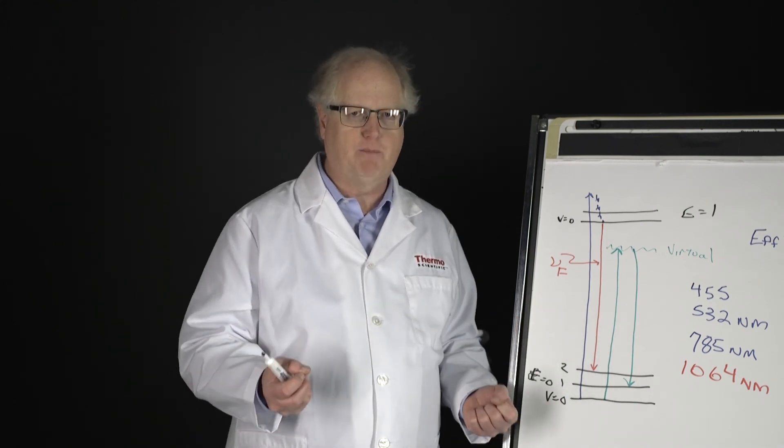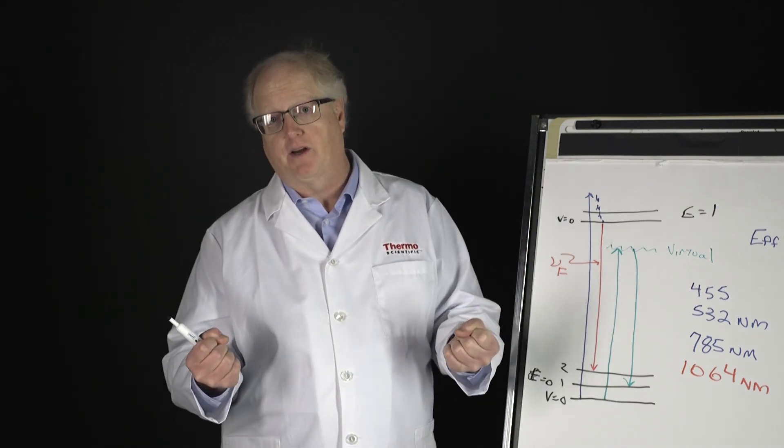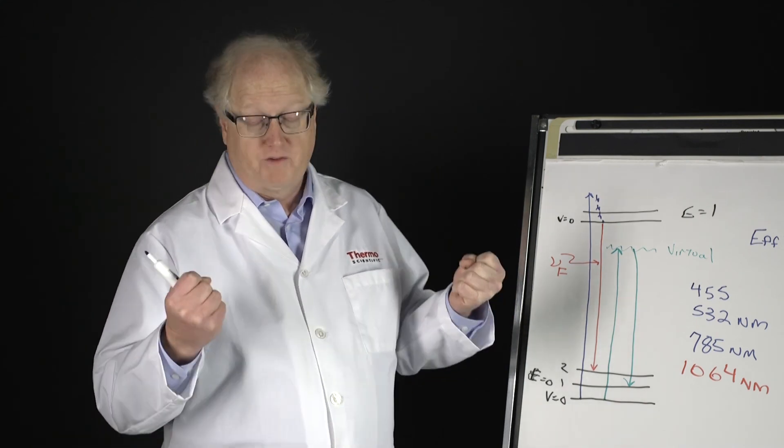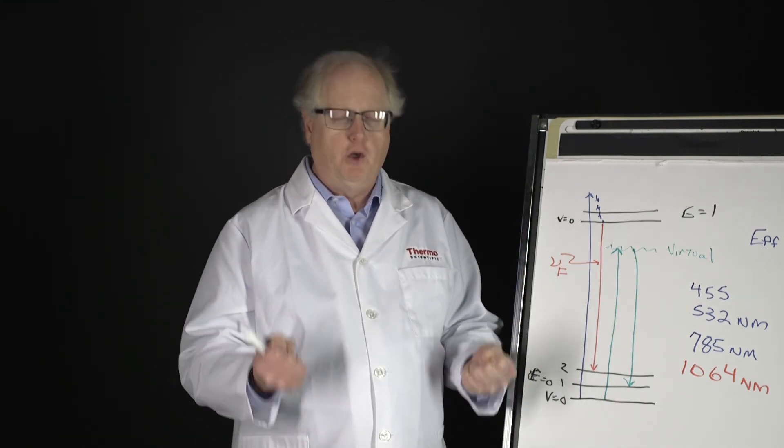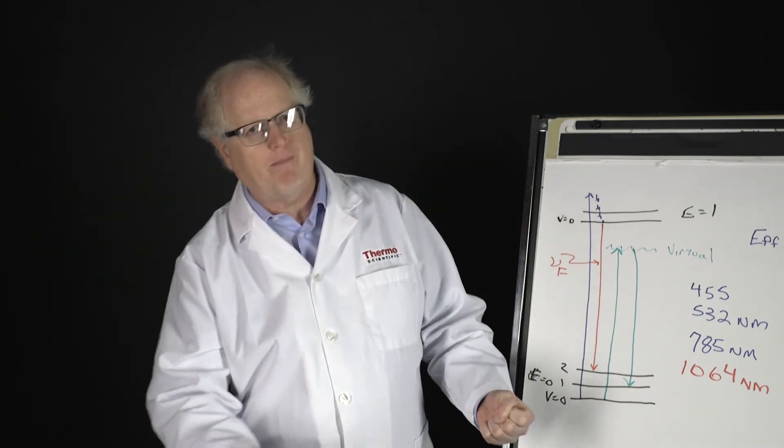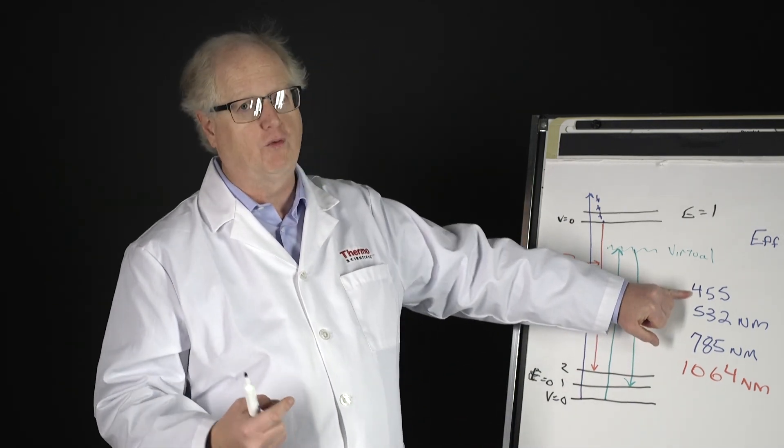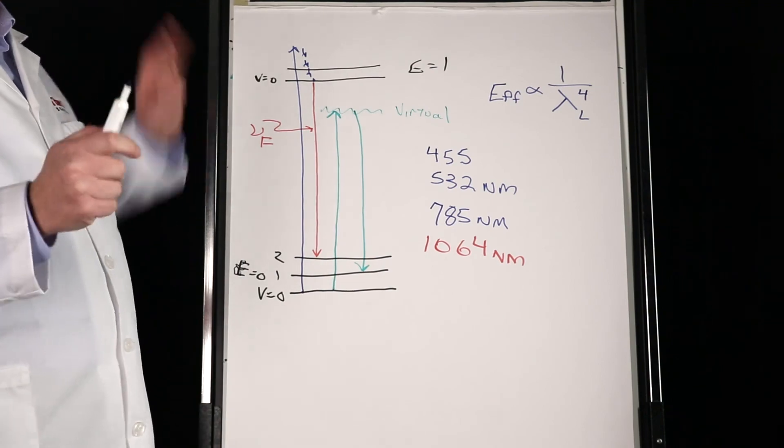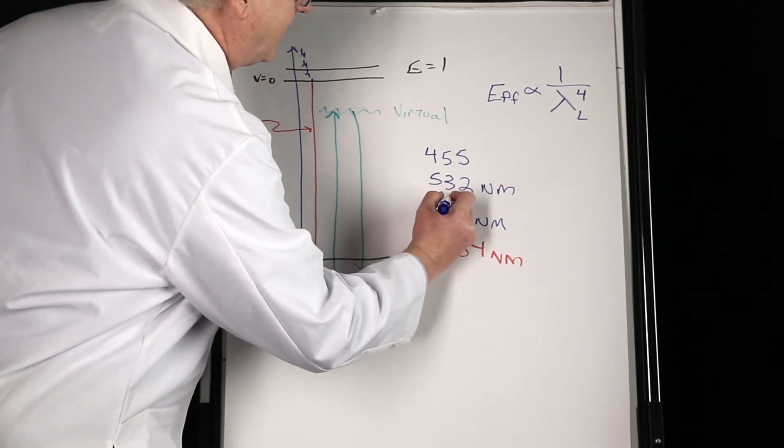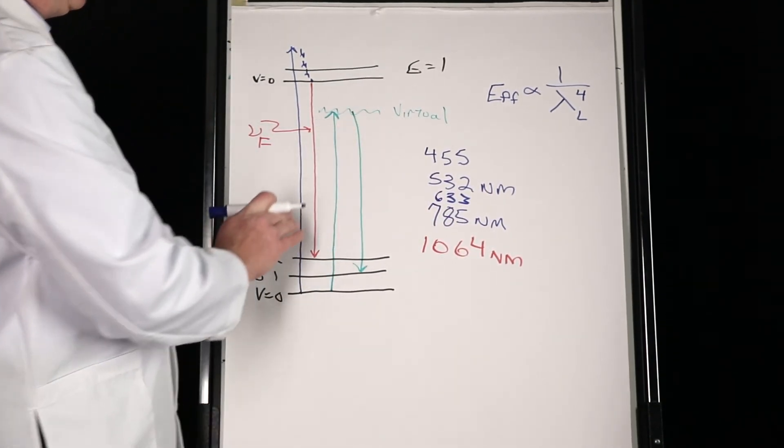And this is why on a system such as the Thermo Scientific DXR microscope, the Raman microscope, or Smart Raman, or the imaging microscope, you have the ability to easily interchange lasers. You can swap them in and out instead of just being stuck with one the whole time, because there may be some systems where 455 works brilliantly, and there are other cases where it doesn't work at all.